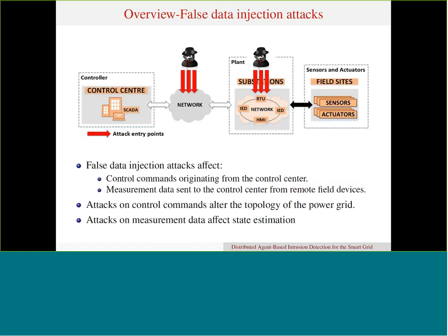But when it comes to attacks on measurement data, these mainly affect state estimation, because a power grid uses a state estimator for information regarding the operating condition of the power grid. The way the state estimator works is that sensory data is sent to the RTU, and then from there it goes on to the SCADA.